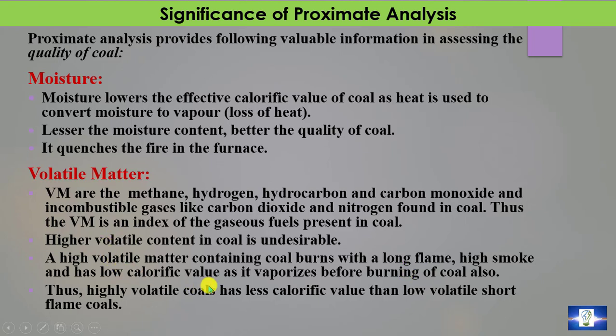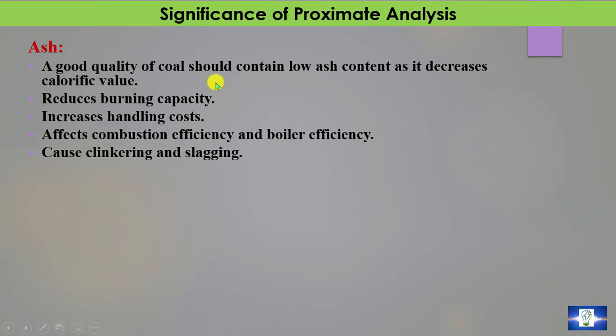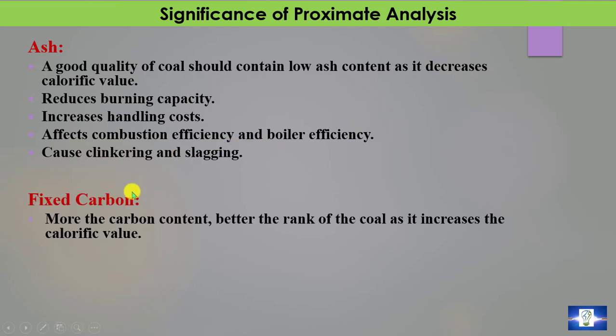Thus, highly volatile coals have less calorific value than low volatile, short-flame coals. A good quality coal should contain low ash content as ash decreases calorific value, reduces burning capacity, increases handling cost, affects combustion and boiler efficiency, and in many cases causes clinkering and slagging. For fixed carbon: more carbon content means more heat content and a better rank of coal, as it increases calorific value.